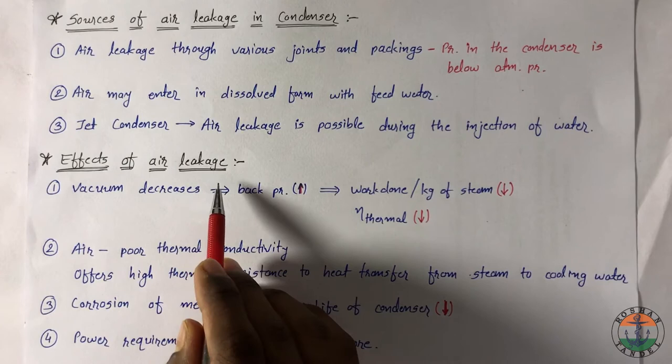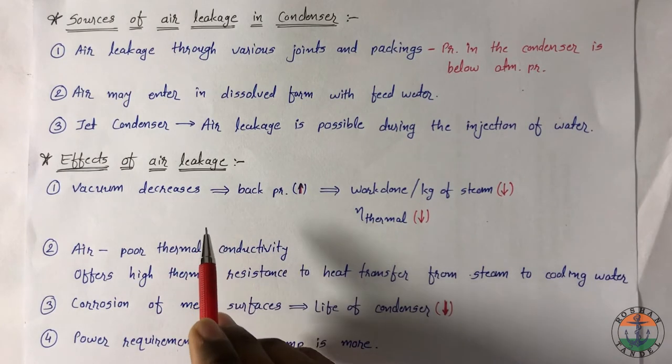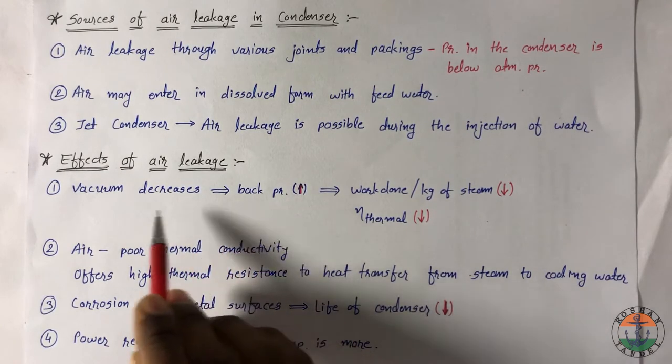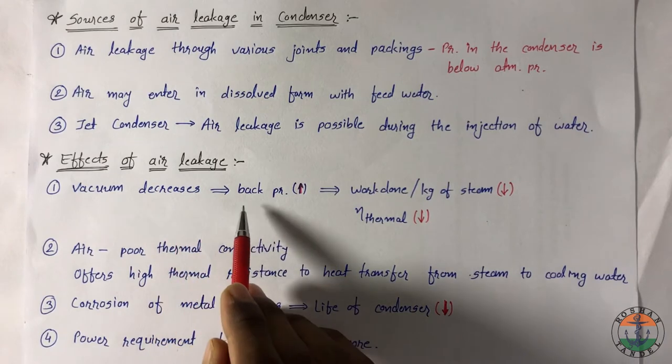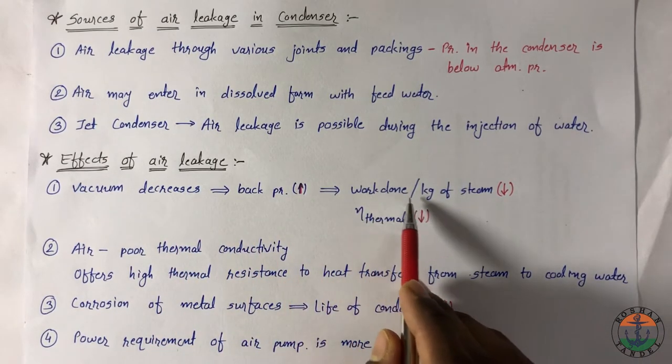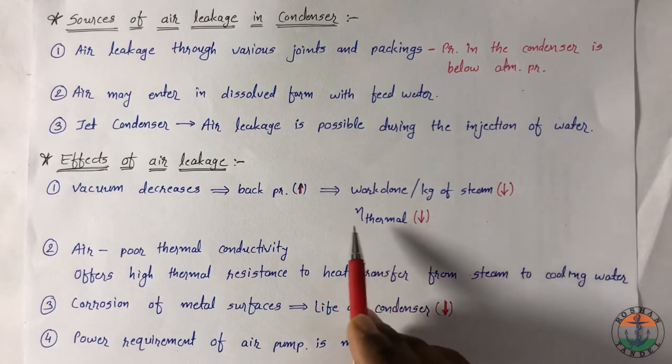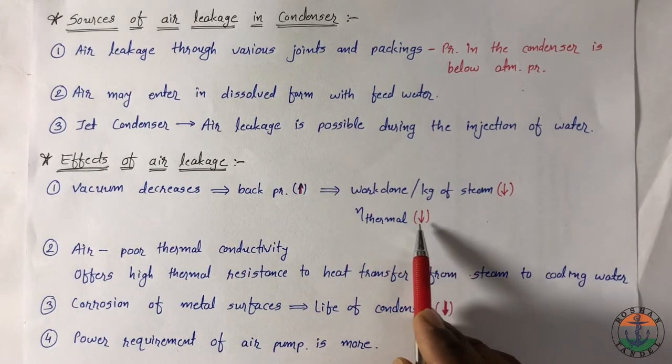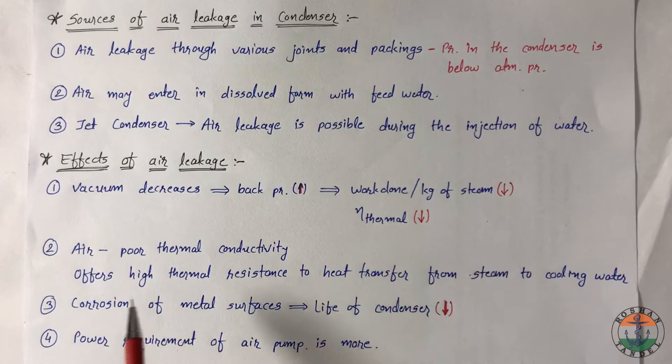Effects of air leakage. Because of air, vacuum in the condenser decreases, so back pressure increases. This reduces the work done per kg of steam and also the thermal efficiency of the plant. Condenser is basically a heat exchanger.